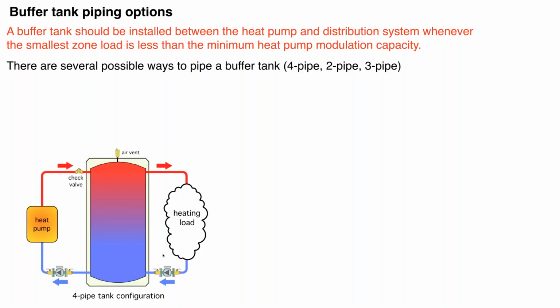Now, the classic way to pipe a buffer tank is what we call a 4-pipe configuration. And this could be a heat pump, this could be a boiler. And you see we've got a circuit with a circulator in it that puts heat into the buffer tank. And then on the other side of the tank, we've got a circuit that takes heat out, all right? Some of the characteristics of that are beneficial and some are not as beneficial. We're going to talk about that in a little more detail. I want to show you the other two configurations, and then we'll go back and take each one of them apart.